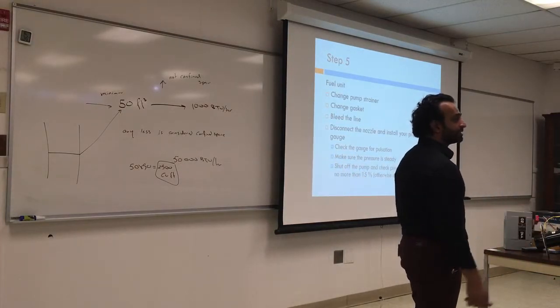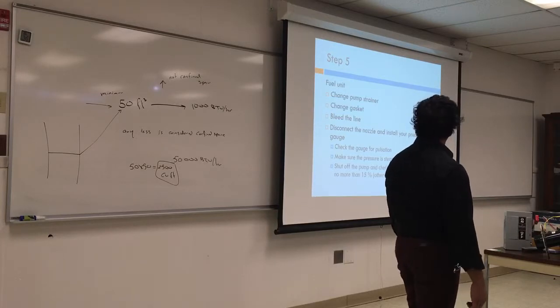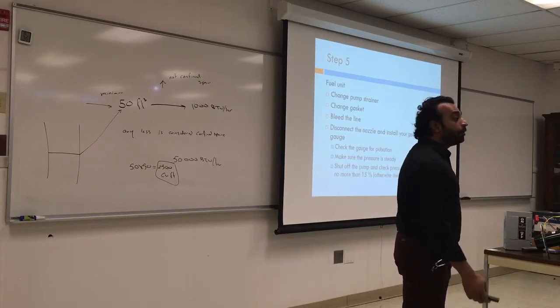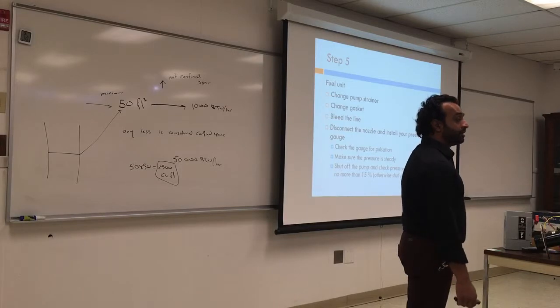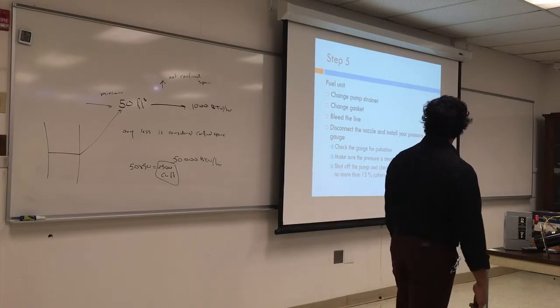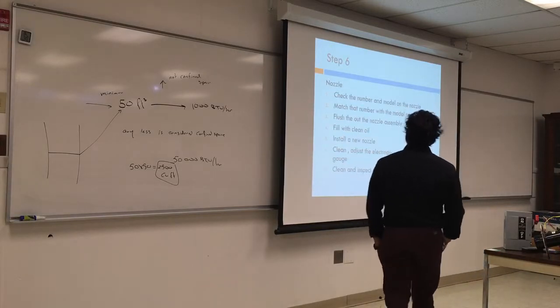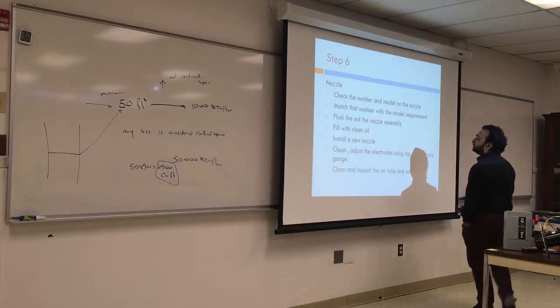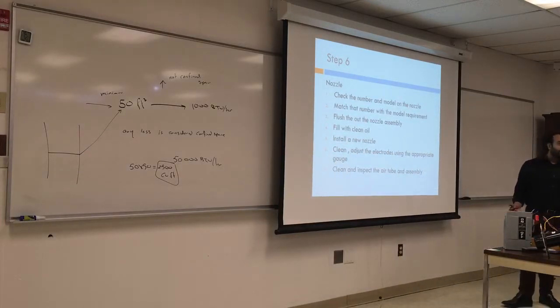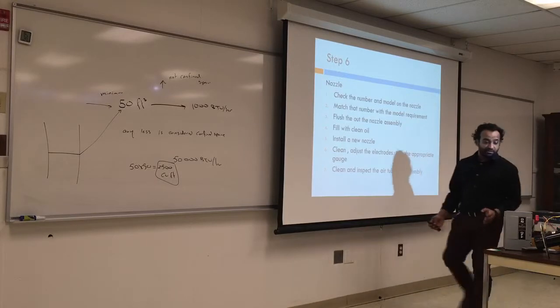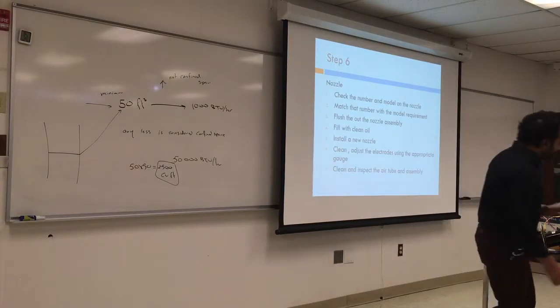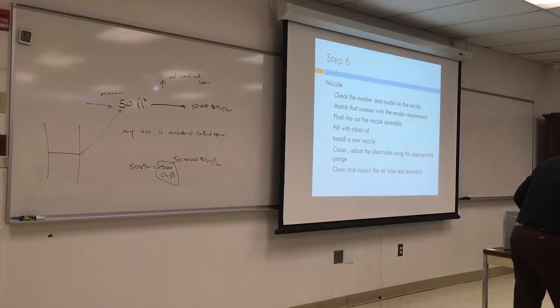If it keeps dropping, there must be a leak in the tank or in the oil line. Or the leak could be in the nozzle. The nozzle is broken or is leaking. Check the number and the model for the nozzle, and match the number with the requirement. So before you take out the nozzle, look at it and make sure it's the same as the outside. Maybe somebody changed it and did not follow the instruction. Make sure they understand why they changed it, and go with the sticker on the burner.